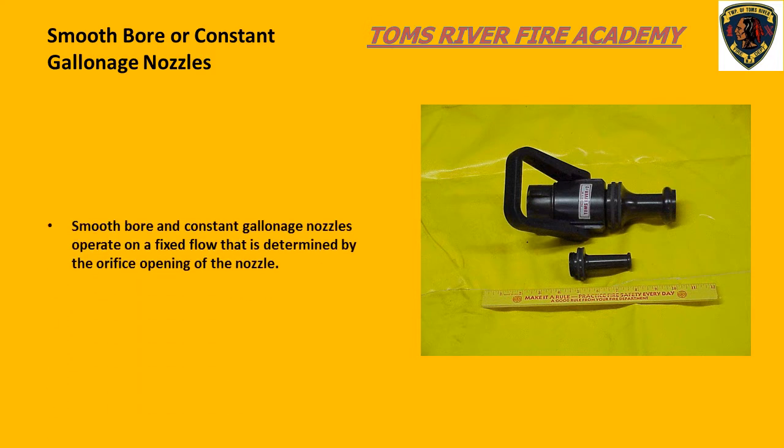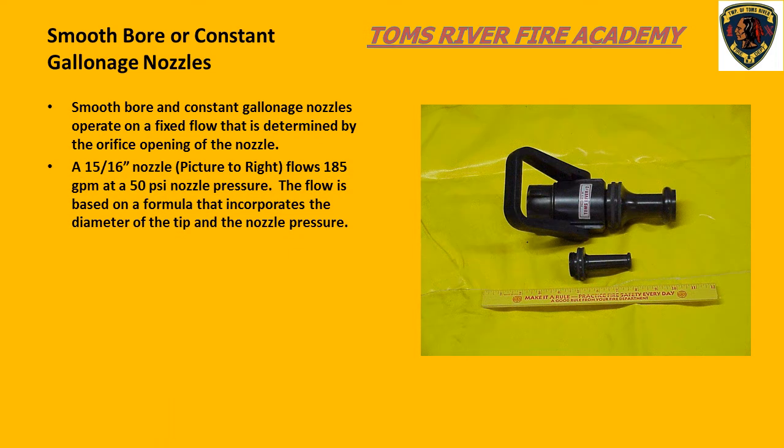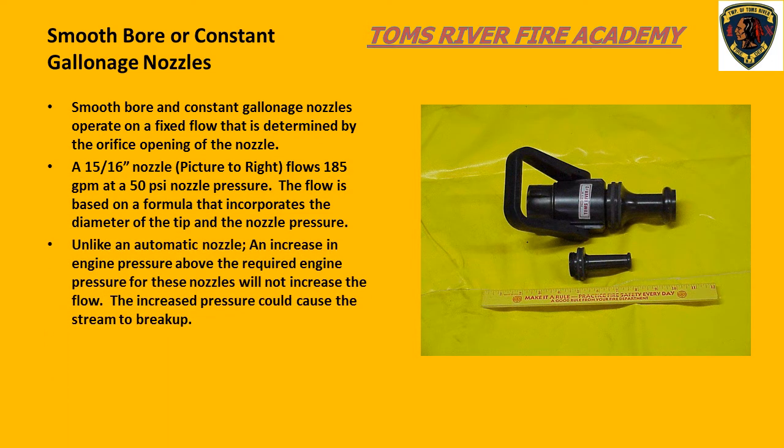Smoothbore or fixed-gallonage nozzles work on a fixed flow determined by the tip size or orifice opening of the nozzle. The 15/16-inch nozzle flows 185 gallons a minute with a nozzle pressure of 50 psi. The flow is based on a mathematical formula using the tip diameter and the nozzle pressure. Unlike an automatic nozzle, an increase in engine pressure above the required engine pressure will not increase the flow — it will more than likely disrupt the shape of the stream and cause it to break up.